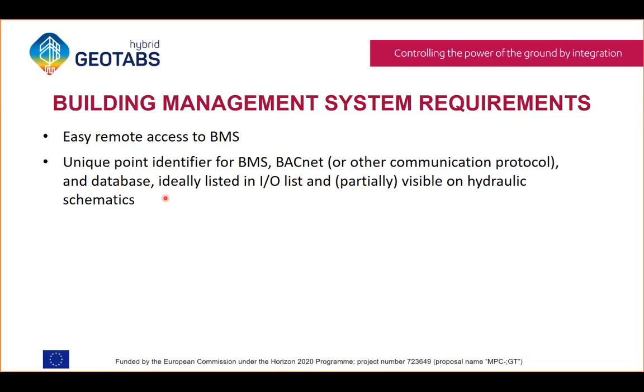Therefore, it's important to create an IO list, and ideally this list would also be visible on the hydraulic schemes, and that installers are obliged to implement that into both the BMS, the BACnet, and the database.